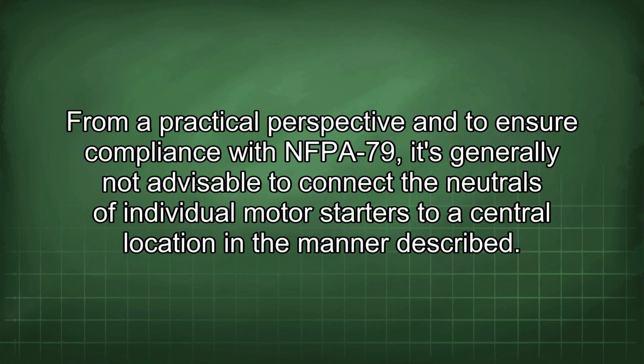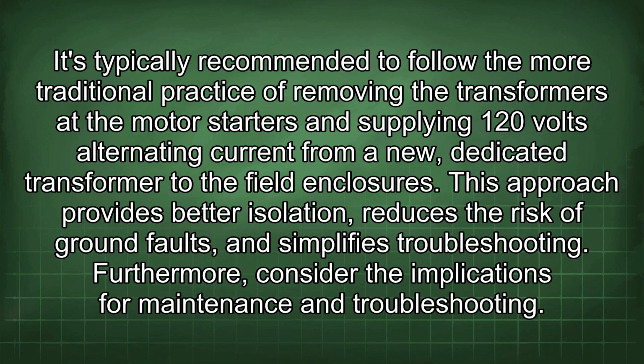From a practical perspective and to ensure compliance with NFPA 79, it's generally not advisable to connect the neutrals of individual motor starters to a central location in the manner described. It's typically recommended to follow the more traditional practice of removing the transformers at the motor starters and supplying 120 volts alternating current from a new, dedicated transformer to the field enclosures. This approach provides better isolation, reduces the risk of ground faults, and simplifies troubleshooting.